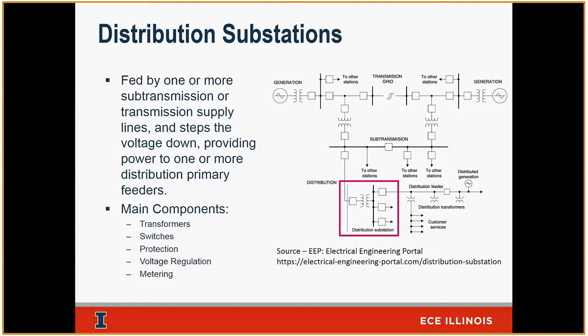So each sub-transmission line will carry a portion of the load you've got in a city. Multiple sub-transmission lines could be picking up an entire city. And those two will also be fed by, say, a 138 kV line. That's a transmission level. So a 138 kV line could come in and then feed those two lines in here. So that's the basics of how we feed the distribution system: transmission line, sub-transmission line, and then we feed our distribution feeders.